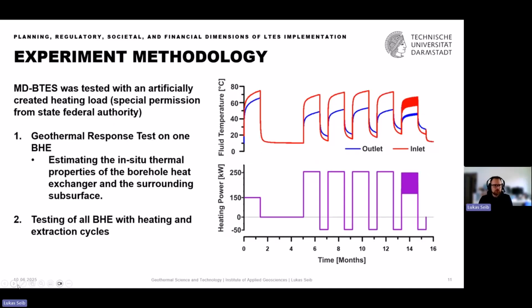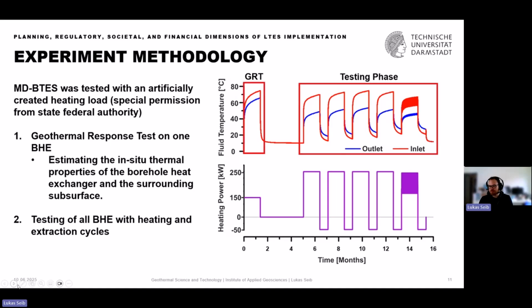Yeah, and then following the drillings, we did quite extensive experiments on the storage system in the past year with an artificially created heating load. As I said, for heating up the subsurface, we needed a special permission from the state authority. So the first thing we did was a geothermal response test, basically, to estimate the in situ thermal properties of the borehole heat exchanger. And then, as a second part, we did quite extensive testing of all borehole heat exchangers with more or less realistic heating and extraction cycles. So we basically heated up the storage and cooled it down in alternating cycles. So 6 weeks of heating, 4 weeks of cooling.